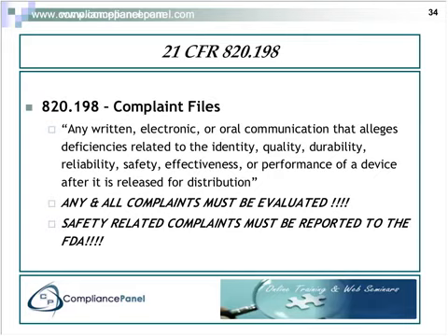Next, we have complaint files, and complaints are usually the main focus of an FDA audit. I know when they've come to my facility, the first thing they ask to see is the person in charge, and then when he has gone through his introductions and given them the escorts, the next thing they want to look at is your customer complaints. As you can see by this slide, the definition of a complaint carries a very broad range of communications, and any and all employees could be the recipient of a complaint.